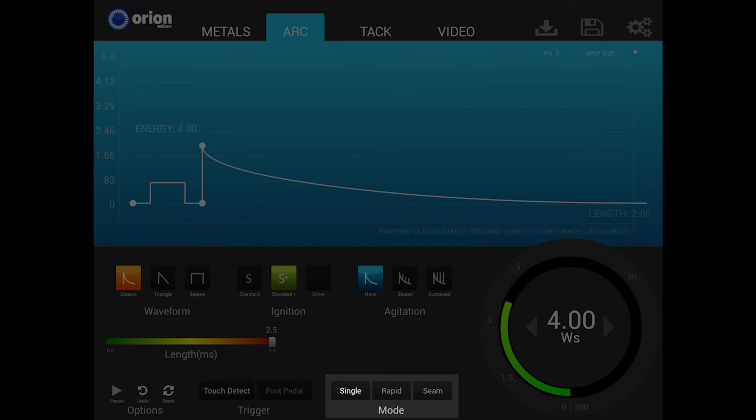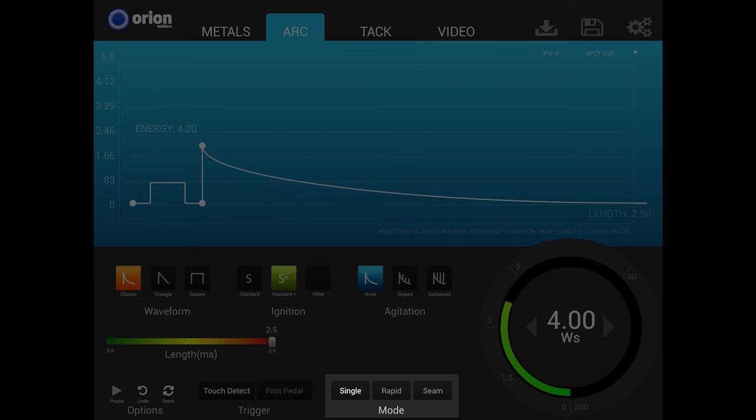Seventh, the energy will turn off. Eighth, the shutter will open. Nine, the tip will return. And ten, the gas will turn off. Making a second weld will repeat this entire process.